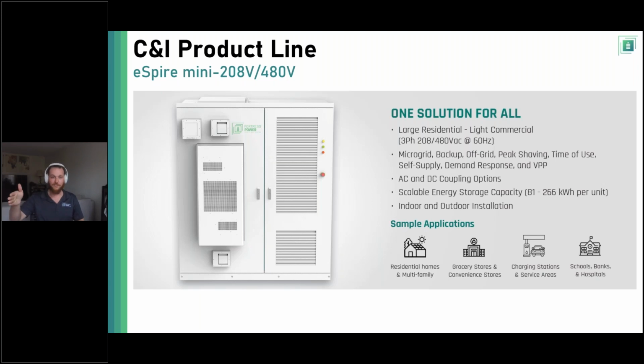Where the 280 starts at 280 kilowatt hours, this system starts at 81 kilowatt hours. Where the eSpire 280 starts at 125 kW of 480 volt power, this system starts at 30 kW of either 208 or 480 volt and can go up to 90 kW of 208 or 480 volt.